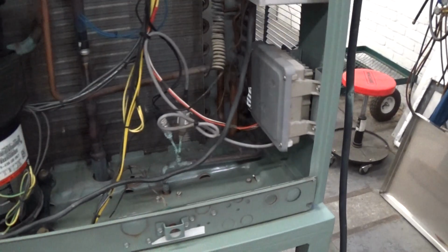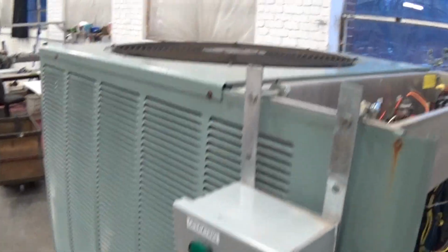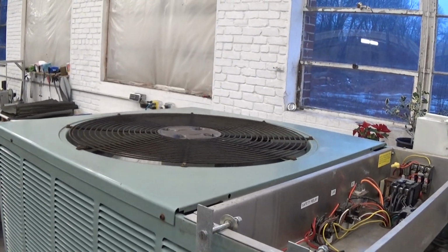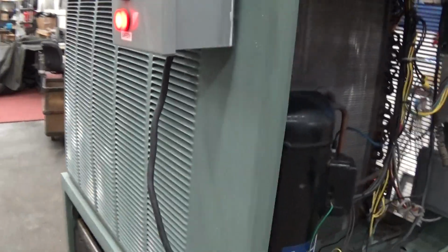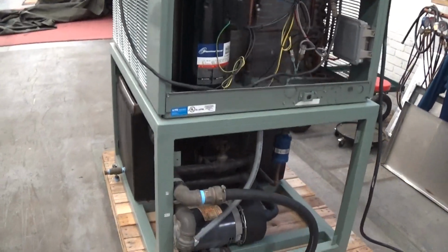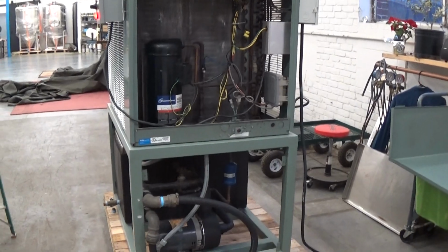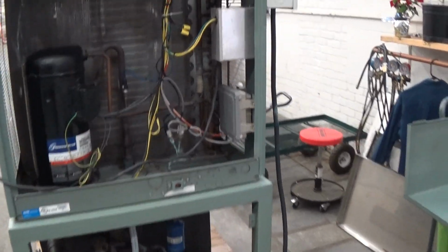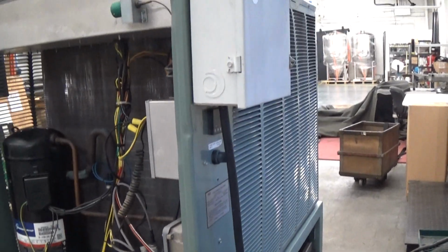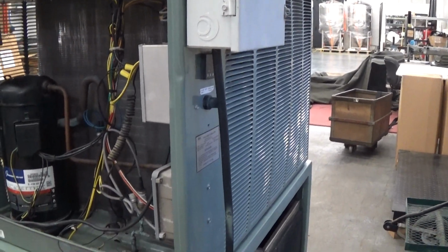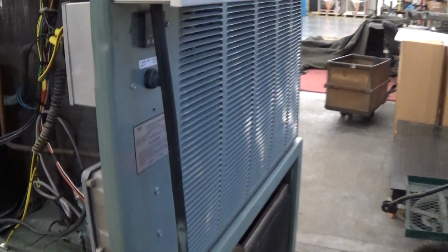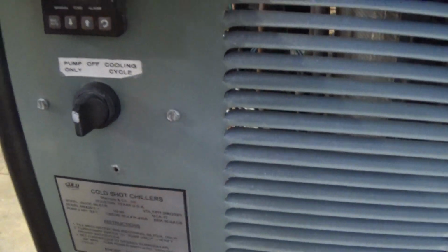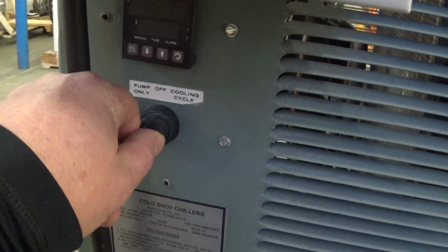For this particular configuration, having those covers off does not inhibit any of the airflow for the upward discharge on this air-cooled chiller. Before I actually turn the pump on, it's worth noting that if you are ever going to turn the chiller on and off, like say you don't want to run it on the weekend, it's good to do it right at the chiller selector switch here. Bring it to the off position here.